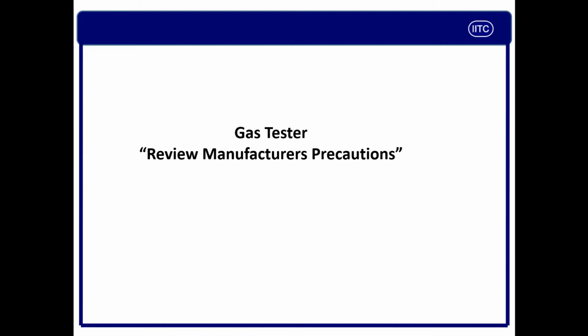Now if you see the gas tester slide, review manufacturer precautions. These are very important points because each manufacturer has got their specific requirements. So say for example, if you are using an instrument of manufacturer A, and after some time you buy an instrument of manufacturer B, you must see what are the precautions mentioned by manufacturer B. The manufacturer's precautions may vary depending on the manufacturer and the type of sensor being used with the gas testing equipment. Because all testing equipments may have different principles of gas testing, may have different kinds of sensors. So this is what you need to understand.